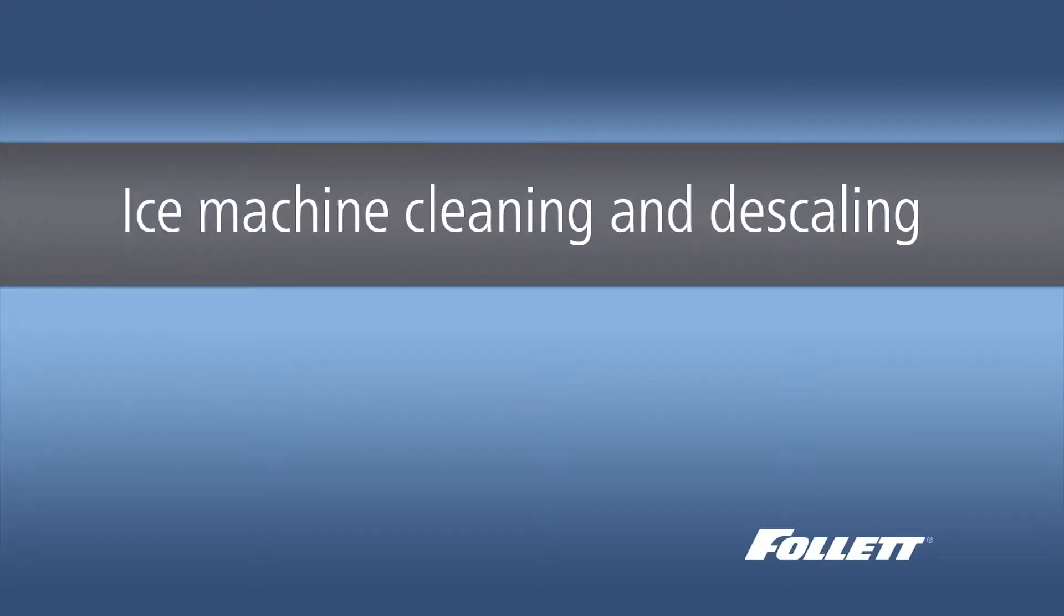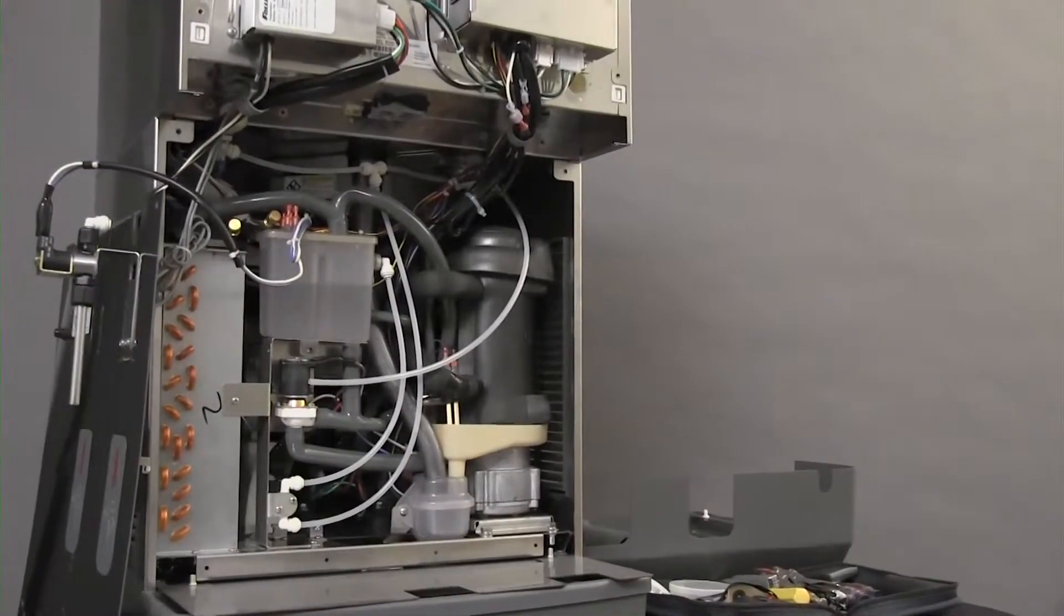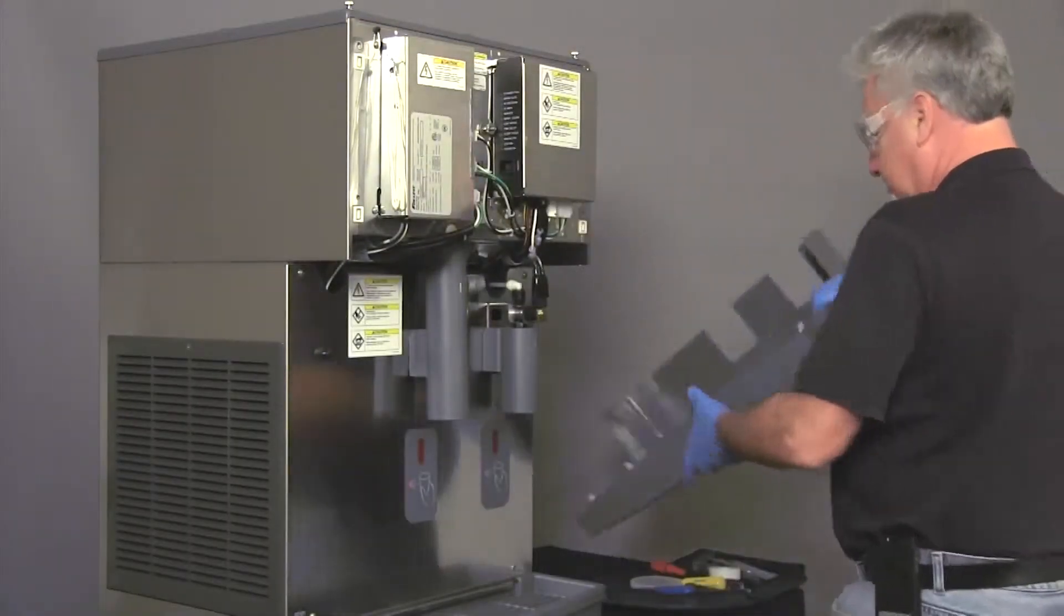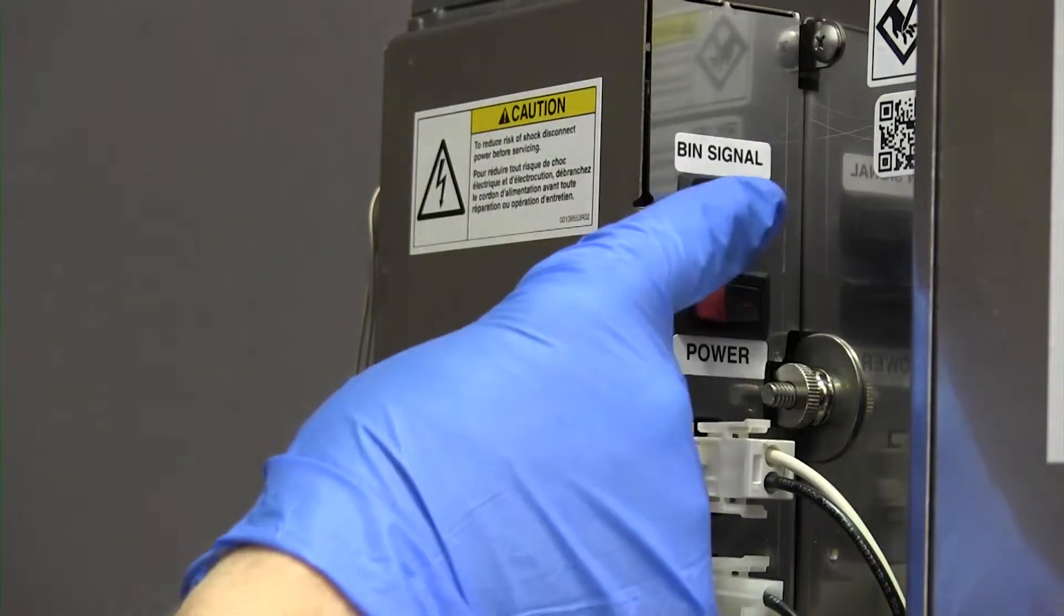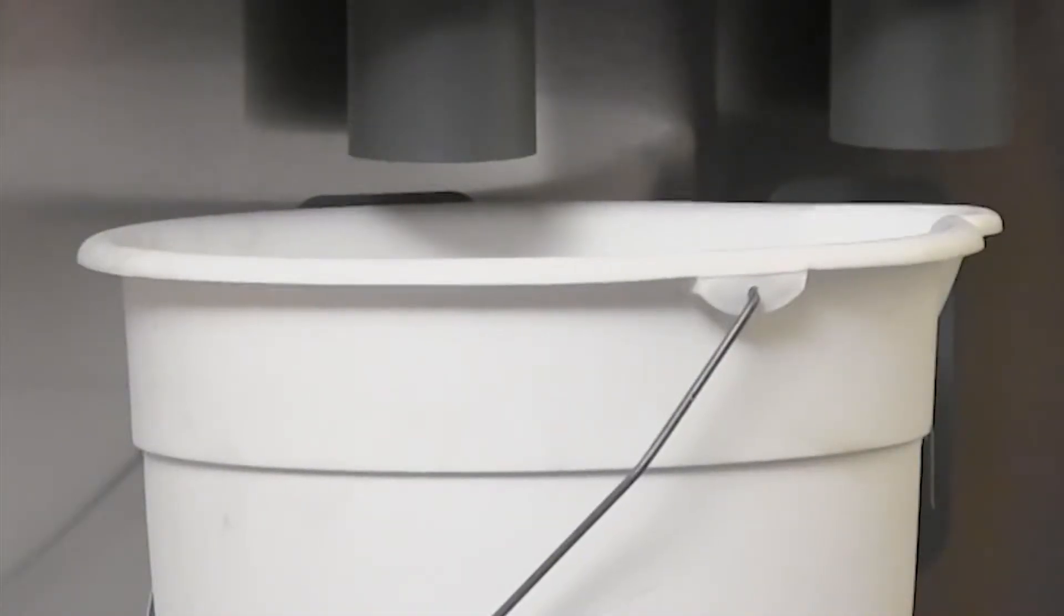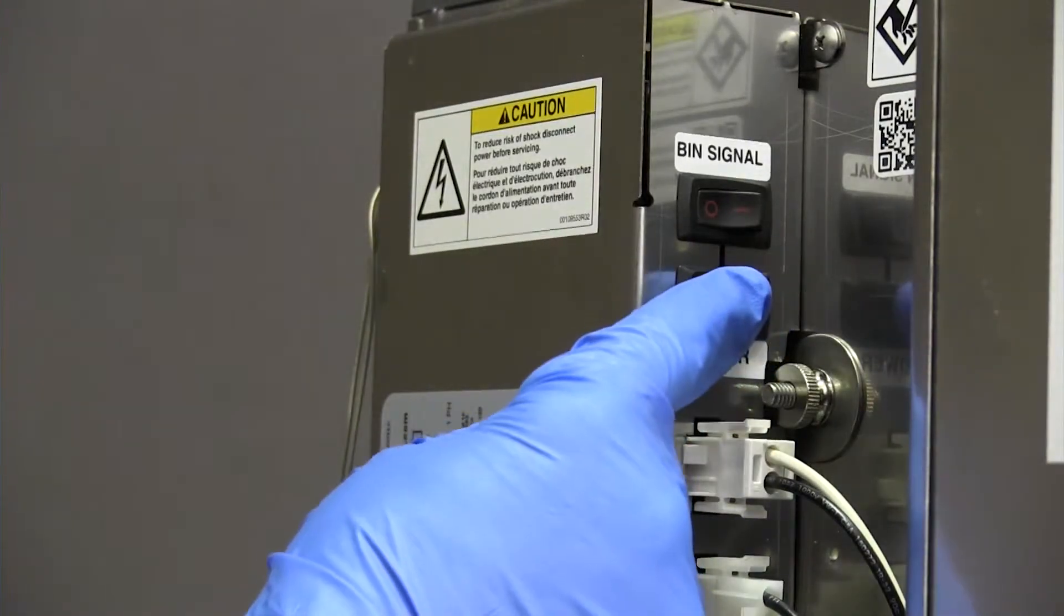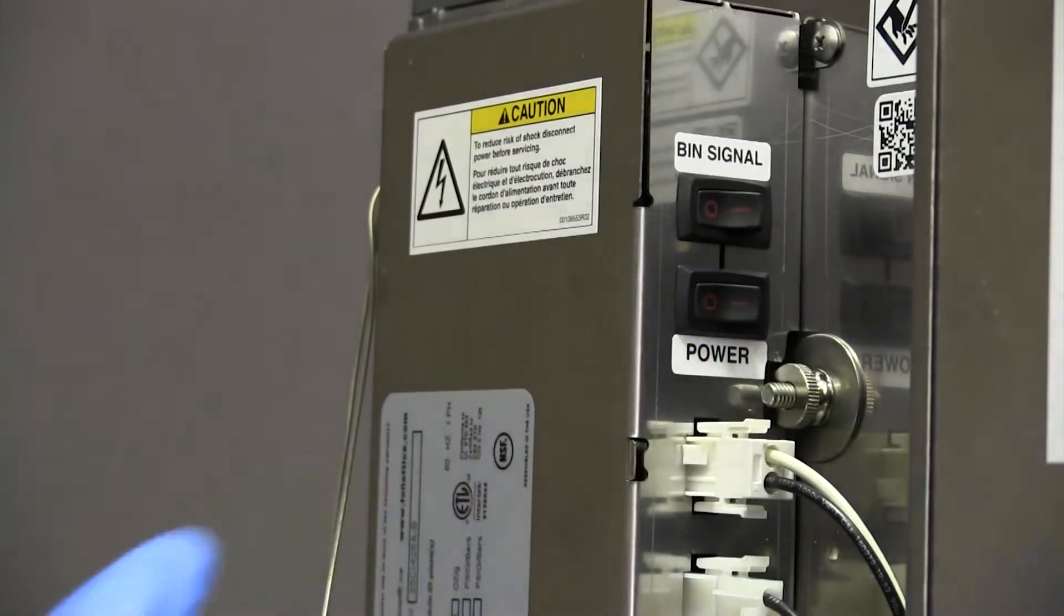The ice machine is located behind the splash panel. Remove the front cover. Turn off the bin signal switch. All of the ice should be dispensed and discarded. Do not put any of this ice back into the ice storage bin after the procedure is complete. Turn off the dispenser power. Always turn off dispenser power before cleaning or removing parts from the ice storage hopper.